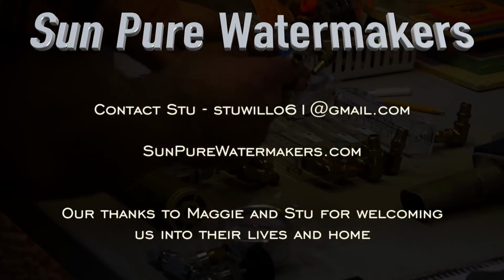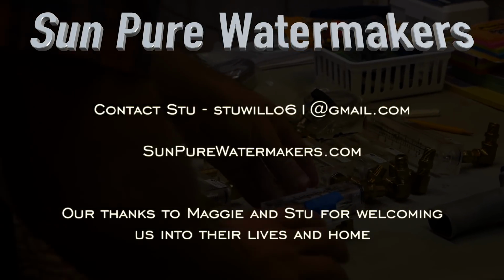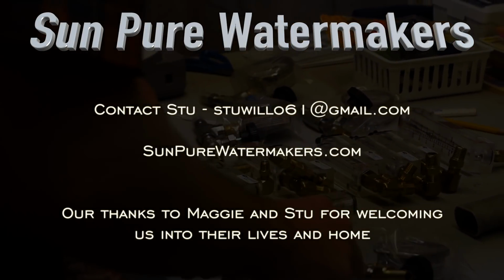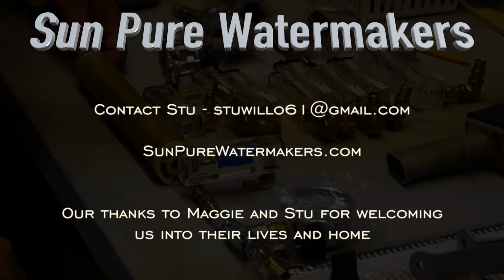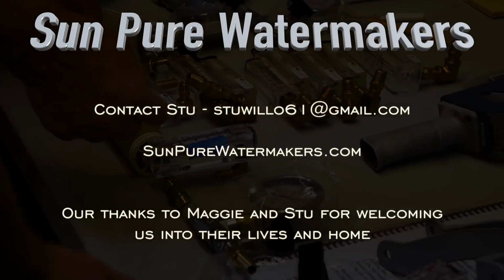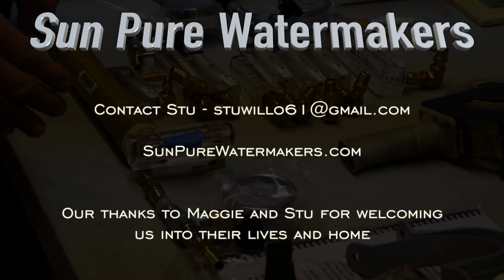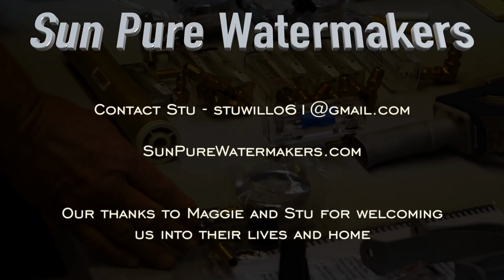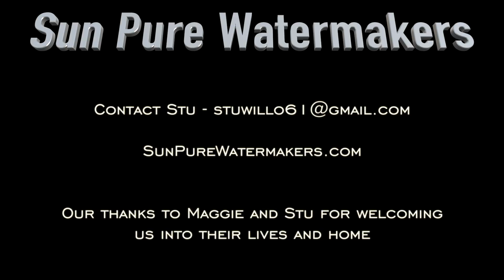Right. And then out of here, is this your product coming out at the top here? That's it. So if these are mounted together here, where is this going to? That's your reject brine. Oh, that is your reject. Okay. Yeah, that would go. So the needle valve's controlling the pressure this way. It does control it that way. Okay. Even though the water's coming in from that direction. The only high pressure you have is from here and through there and through the high pressure stainless steel braid line.